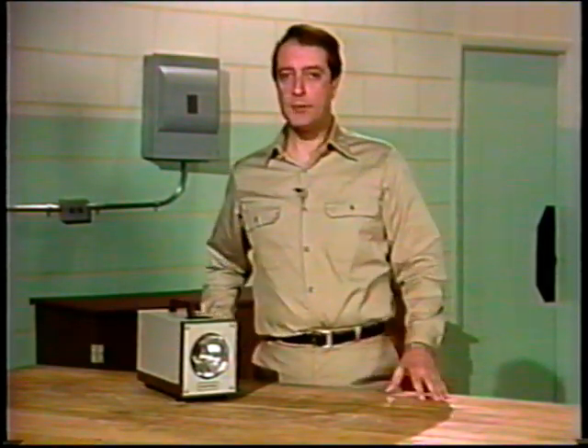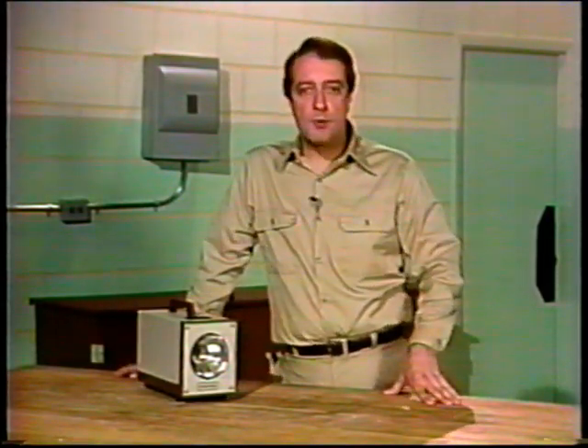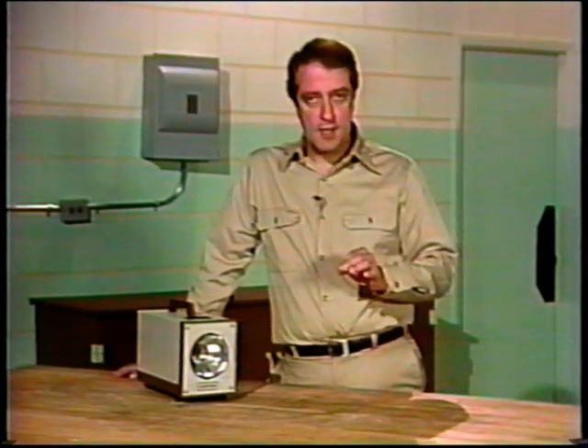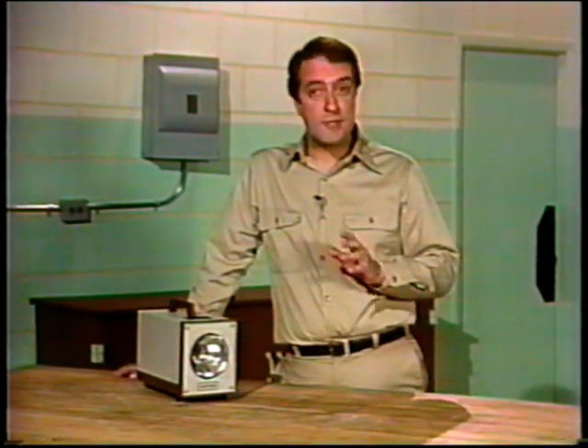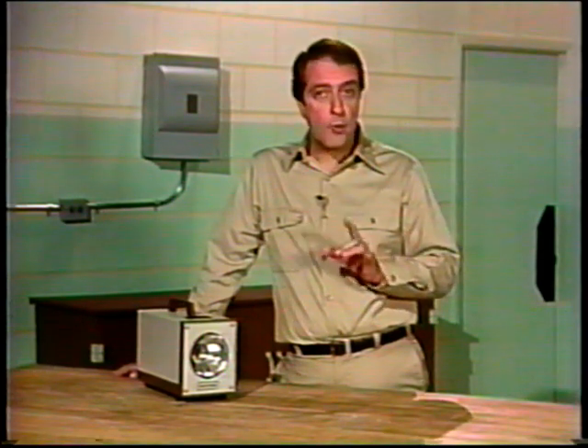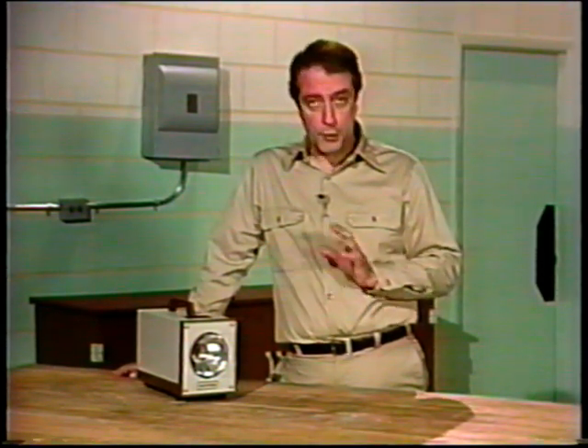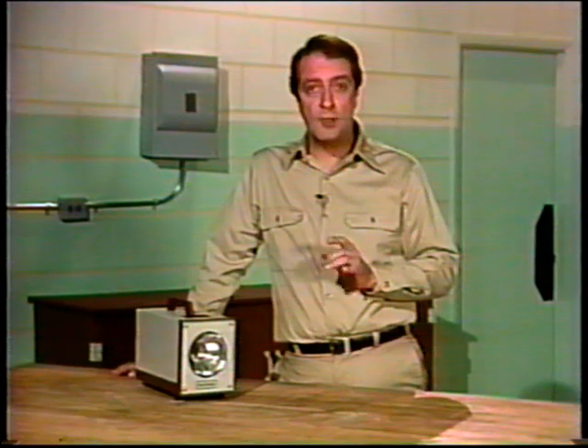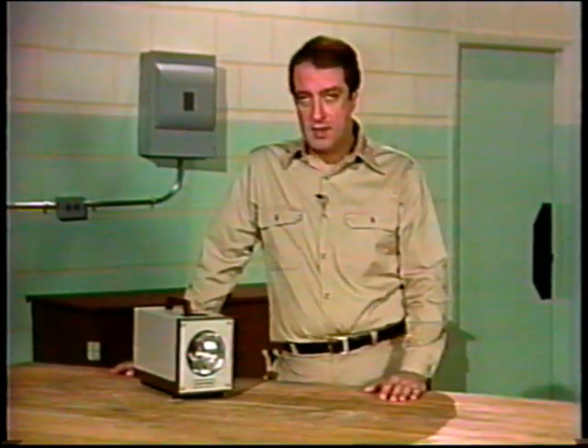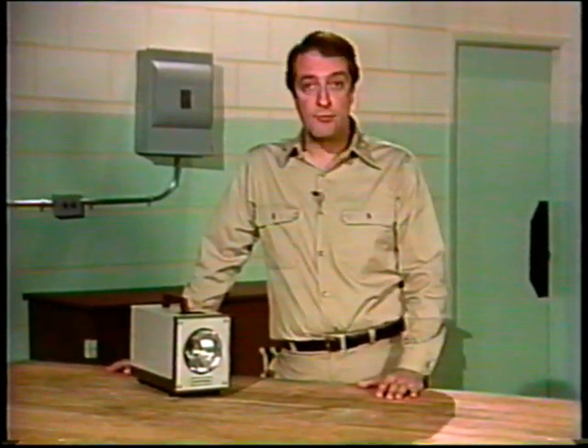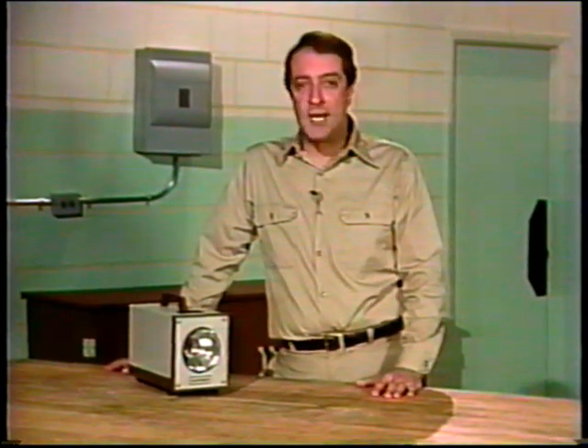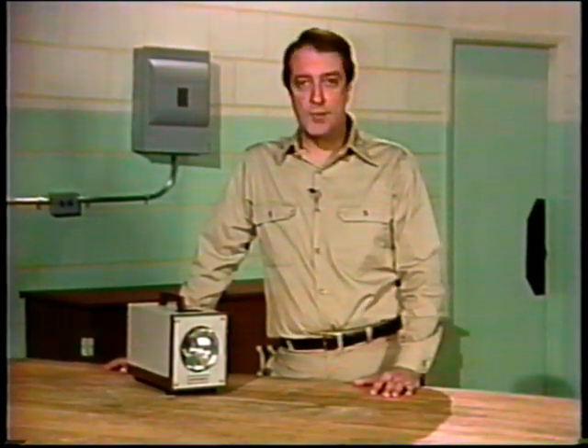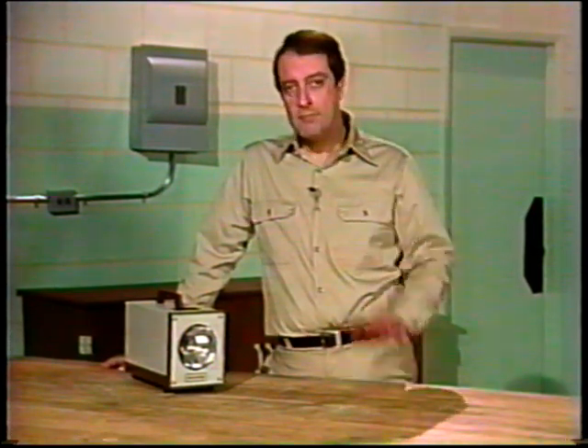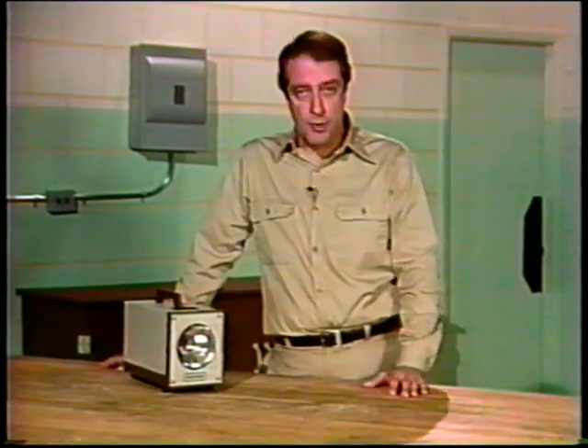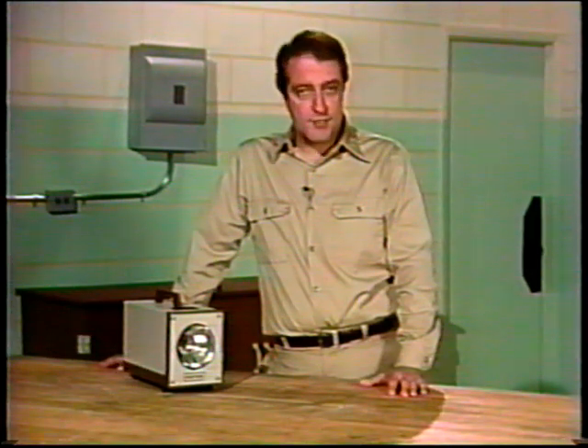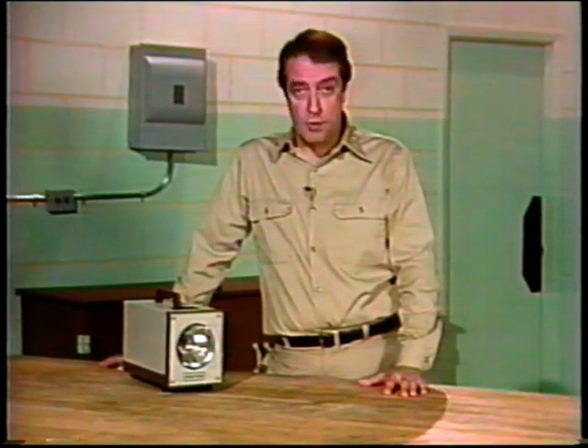Rotor lag also occurs when the strength of the rotor's electromagnetic field is decreased. The electromagnetic field in a rotor is generated by direct current flowing through the rotor poles. The current flowing through the rotor windings is called excitation of the rotor. By decreasing the direct current flow through the rotor windings, we underexcite the electromagnetic field. In other words, the field becomes weaker. By increasing the direct current through the rotor, we overexcite or strengthen the electromagnetic field of the rotor.